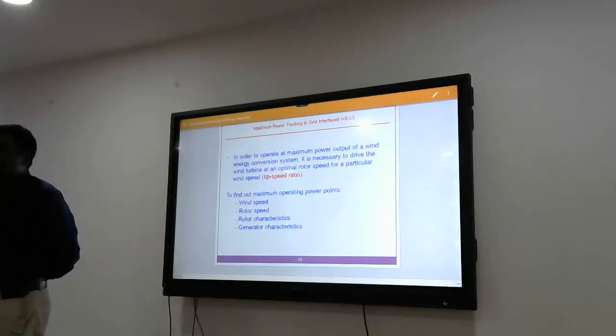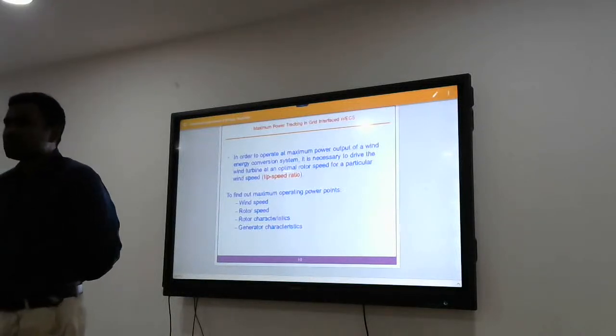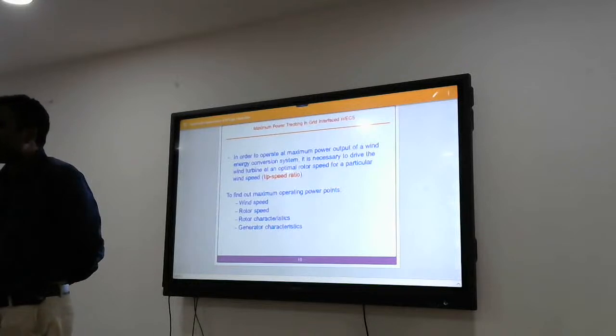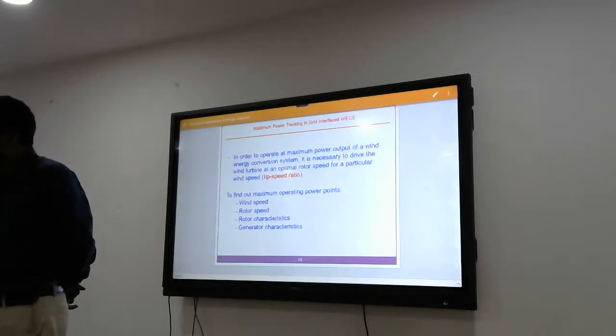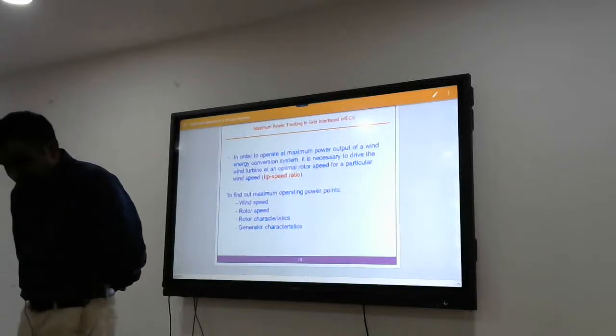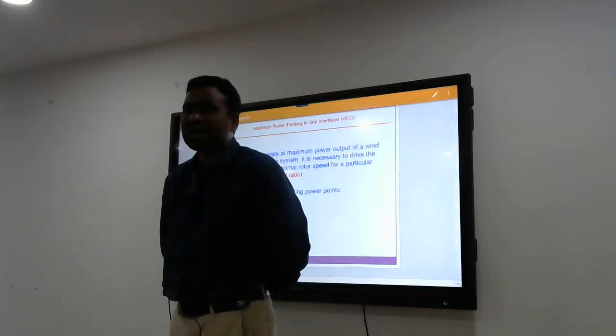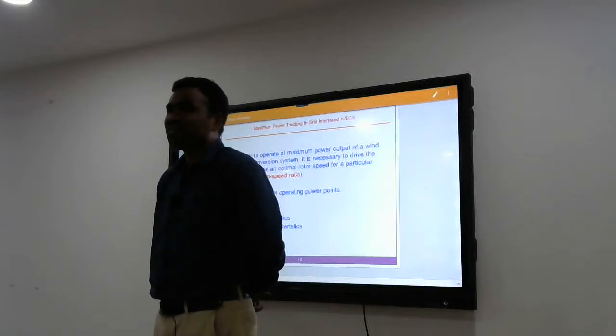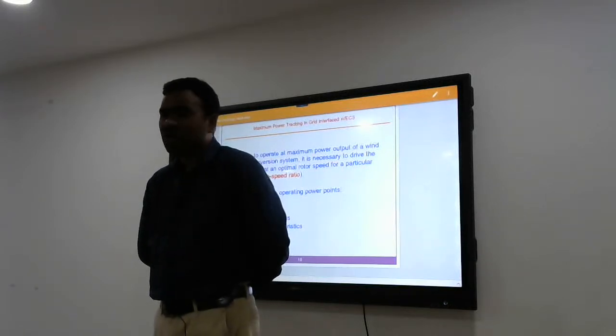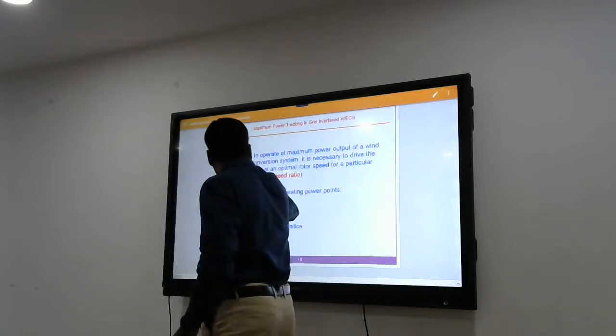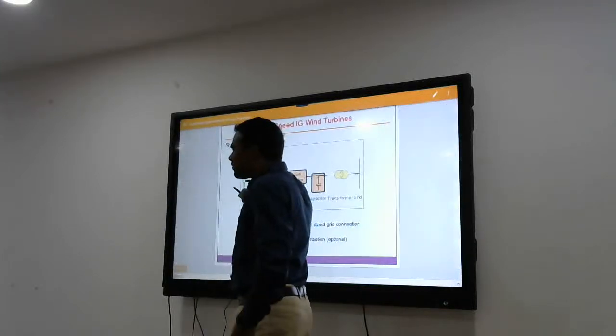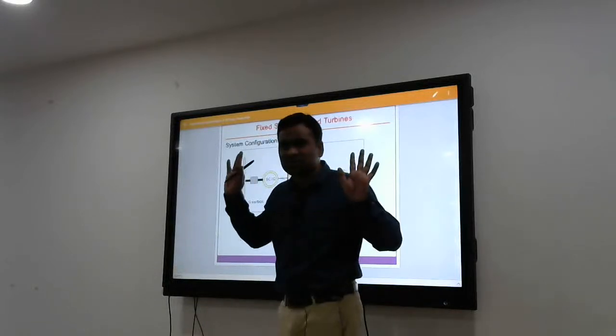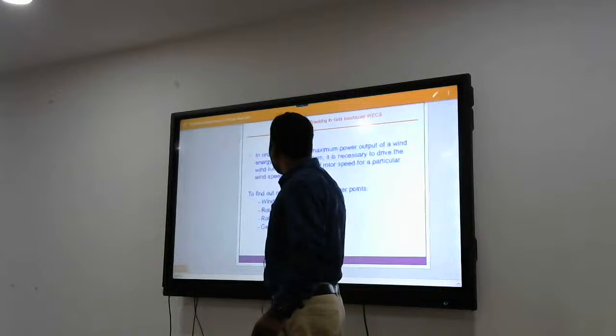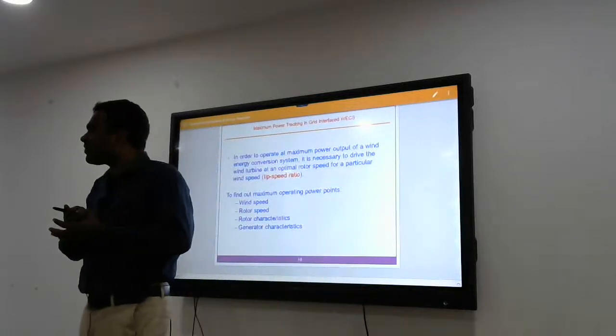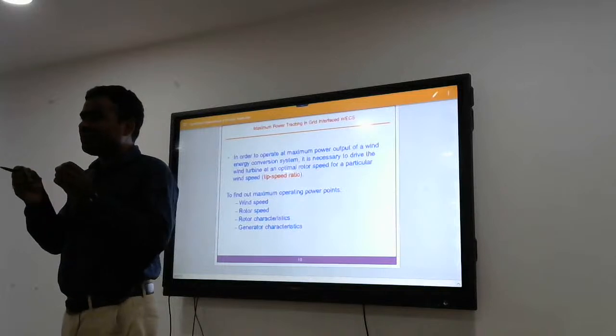Now comes the variable speed wind turbines. In variable speed wind turbines, as I have mentioned before, if your wind speed is changing, you have to change the rotor speed. If you are running at different speeds, then the frequency is obviously different. In the previous case, you are running at fixed speed, so your frequency is good, 50 Hz. Now for this variable speed wind energy conversion system, for achieving MPPT, you are running at different rotor speeds.